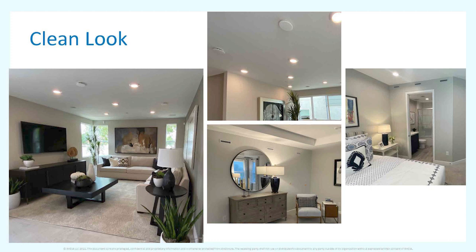So you'll see there's several in a room, and on the left here, there's 4 on the ceiling. The reason for doing that is because obviously we have a smaller diameter duct, so we need more ducts per room. And running more ducts per room gives you a different advantage. It allows you to distribute that air more efficiently into the room, from more points. You get better air mixing because of that, and as a result, the room will feel more comfortable. There's less chance of hot and cold spots, and again, because they're out of the way, there's no risk of anything being blocked or obstructed.